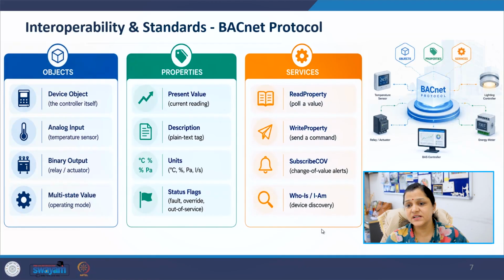The interoperability and BACnet protocol. Modern BAS projects rely heavily on interoperability. This means devices from different manufacturers should communicate with each other. The most widely used open protocol for this purpose is BACnet. BACnet was developed under ASHRAE standard 135. BACnet communication is organized using objects, properties, and services. For example, an analog input object may represent a temperature sensor. A binary output object may represent a relay or actuator. Each object contains properties such as present value, unit, description, and status flags. BACnet services allow devices to exchange information.